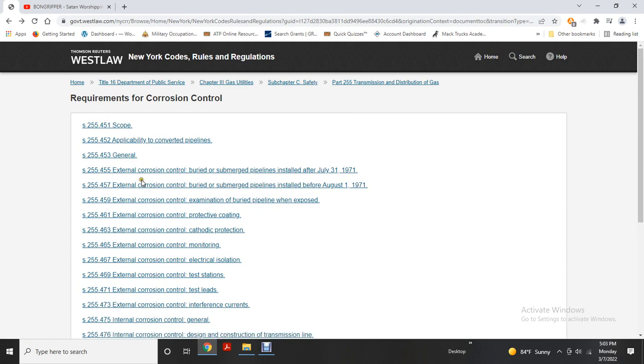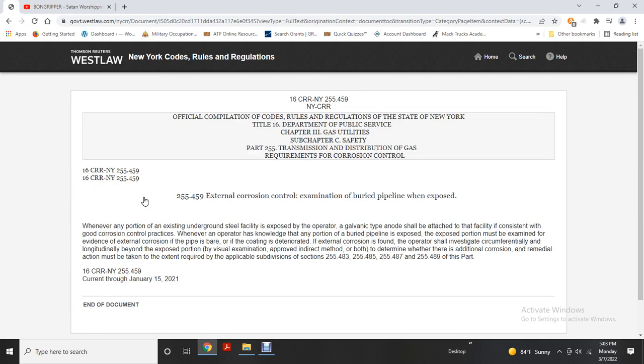Examination of buried pipeline: whenever a portion of an existing underground steel pipeline is exposed, the operator shall attach a galvanic-type anode to the facility, consistent with good corrosion control practice. Whenever any buried pipeline portion is exposed, the exposed portion must be examined for evidence of external corrosion — where the pipe is bare or the coating has deteriorated. If external corrosion is found, the operator shall investigate circumferentially, with remedial action taken as required under sections 255.483, 255.485, 255.487, and 255.489.